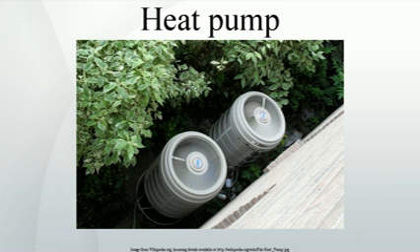In cooling mode, a heat pump's operating performance is described in the U.S. as its energy efficiency ratio, EER, or seasonal energy efficiency ratio, SEER, and both measures have units of British thermal unit per watt-hour. 1 British thermal unit per watt-hour equals 0.293 watts per watt. A larger EER number indicates better performance. The manufacturer's literature should provide both a COP to describe performance in heating mode, and an EER or SEER to describe performance in cooling mode.